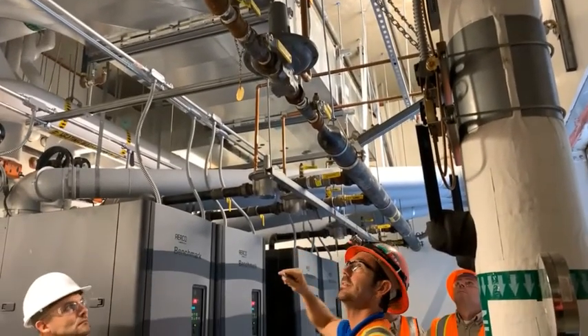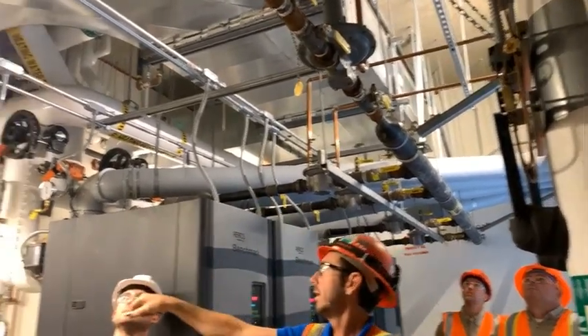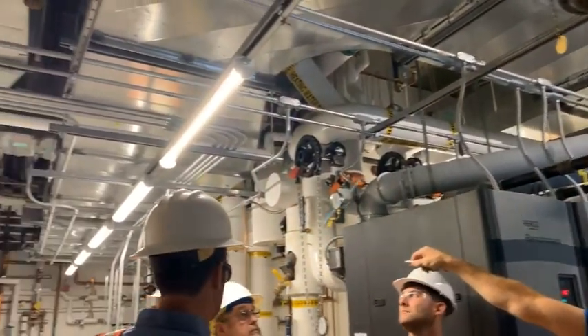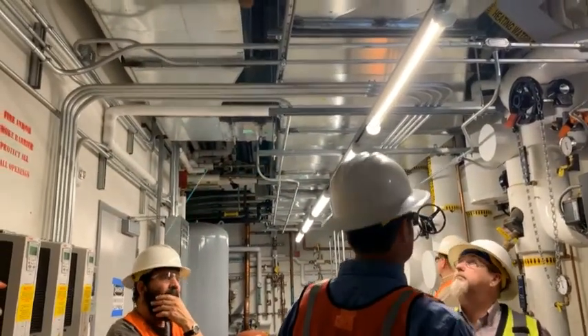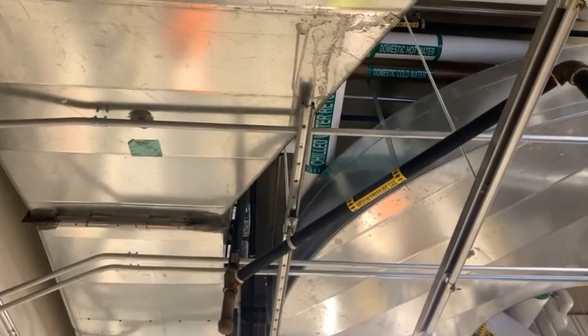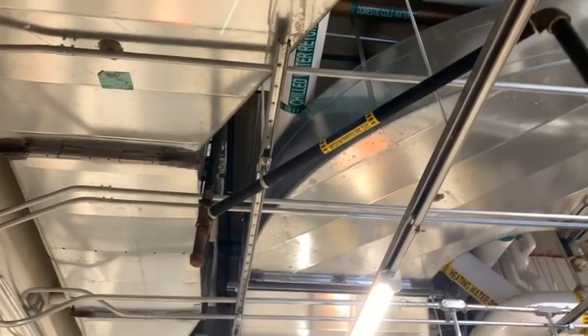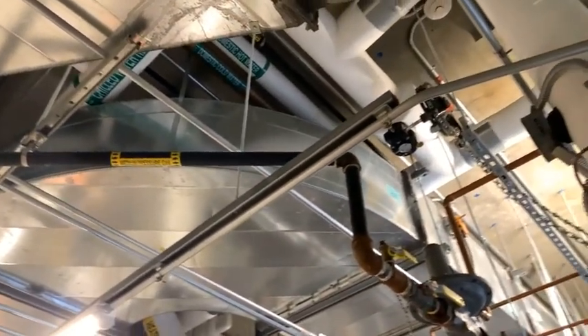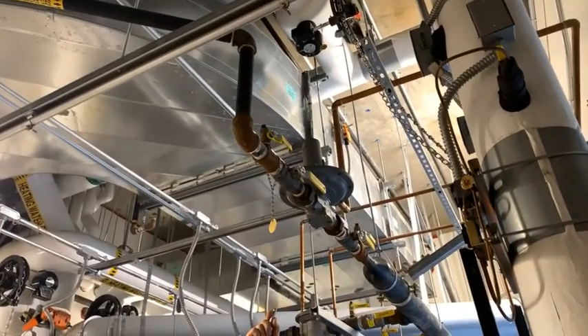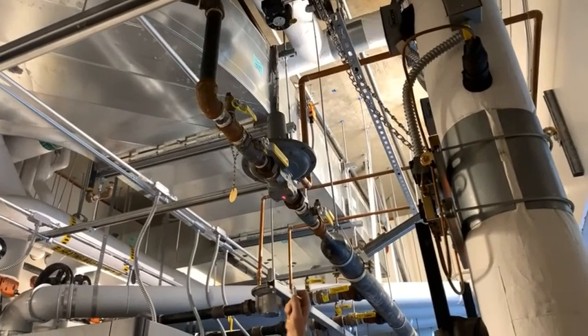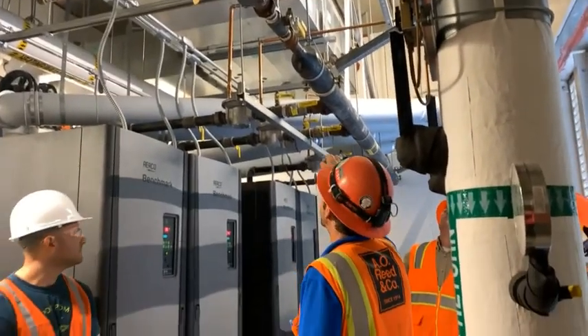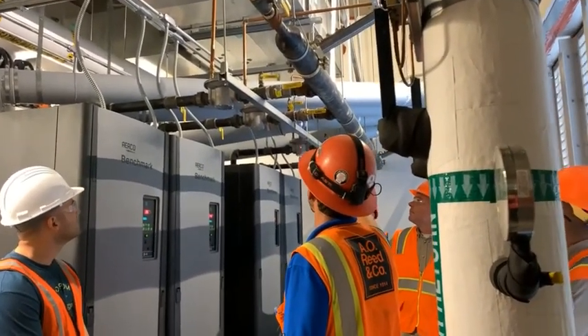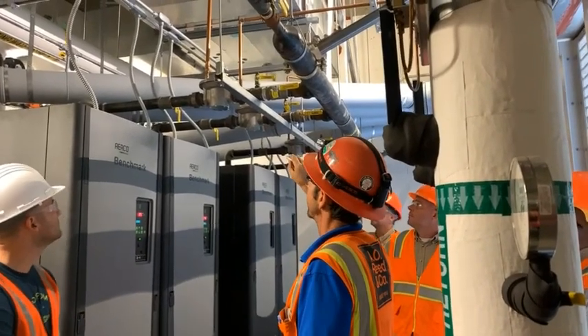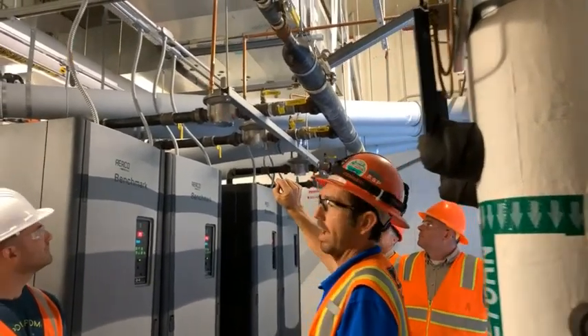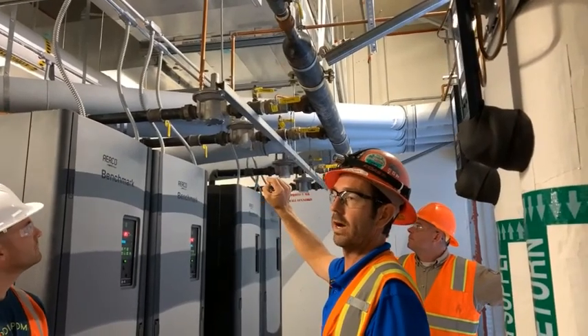And then now that we're up in the ceiling, we'll look at the gas again. The gas comes in at that back wall that we saw and comes up. It's going to be this drop right here. This is that medium pressure gas line I was talking to you about outside. Okay, it comes over. We have 2 shutoff valves in front of the pressure reducing valve. And then we come out here and we go through 4 more gas valves. These gas valves are not 100% shutoff valves. They are flow.